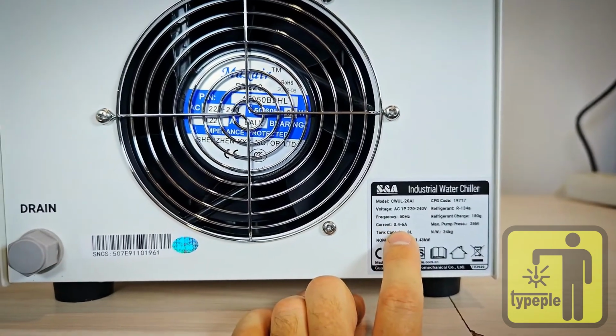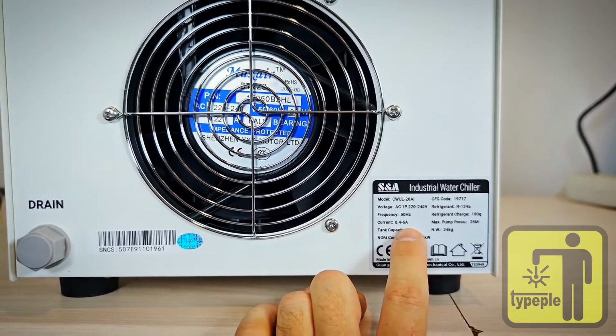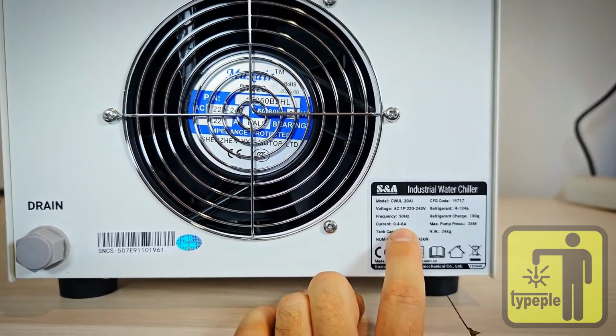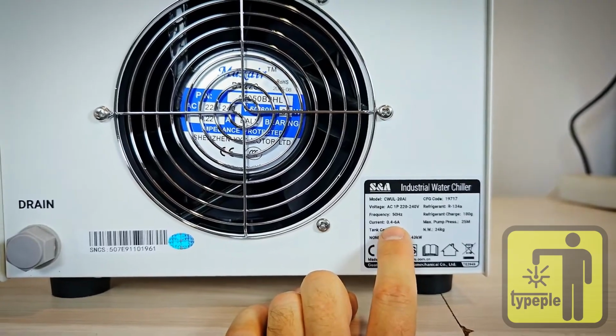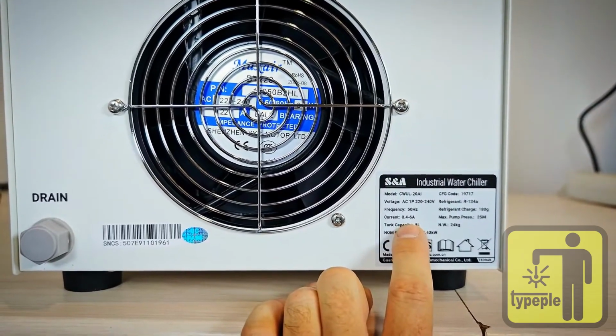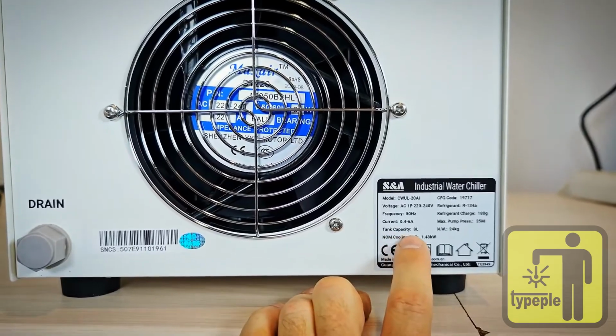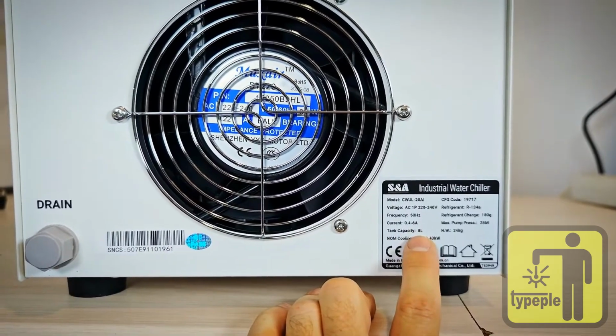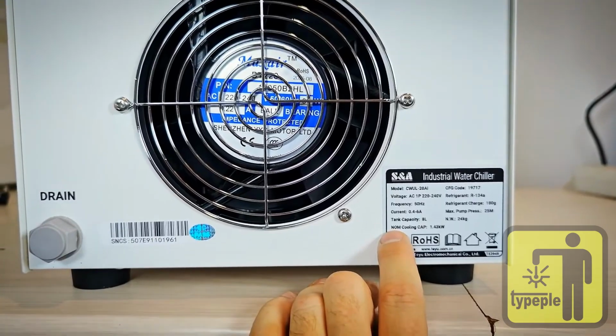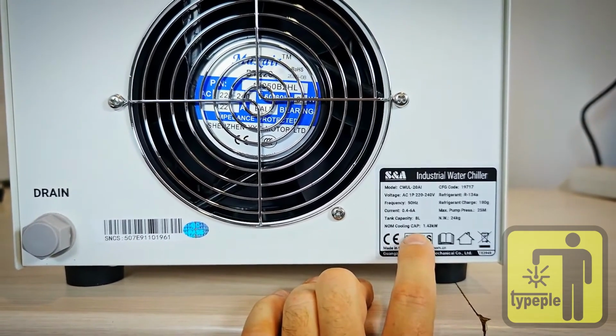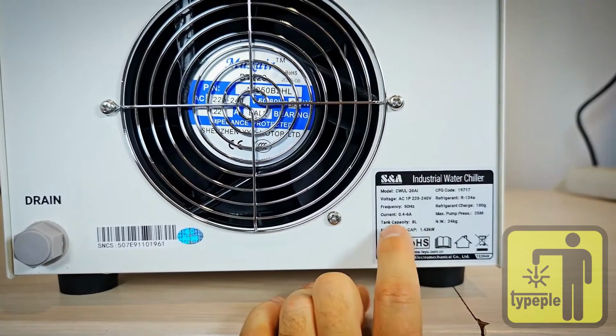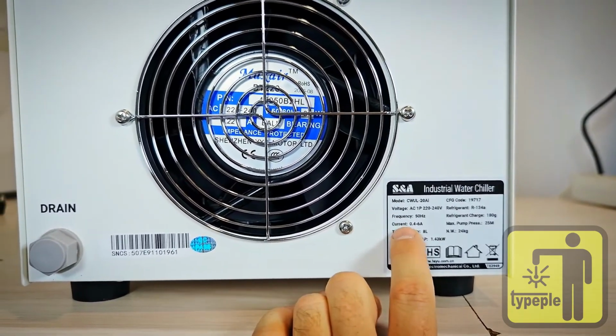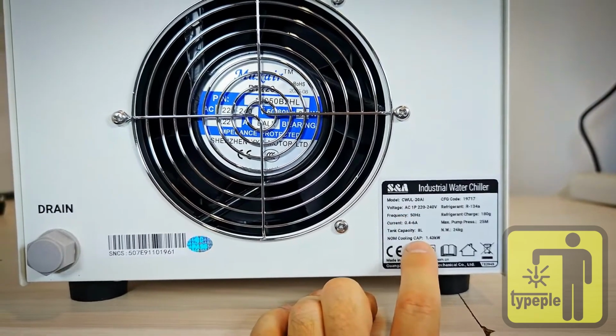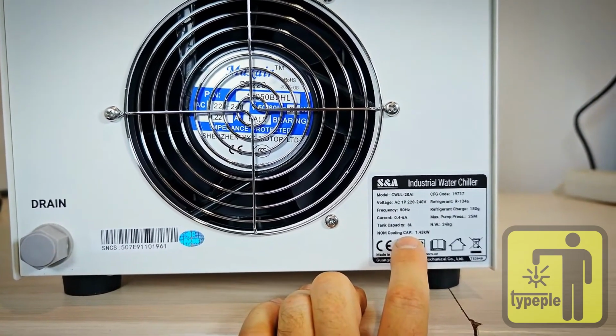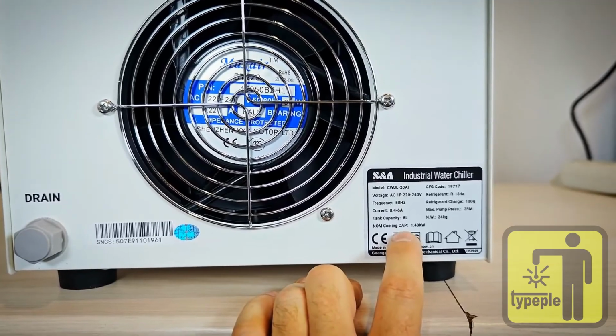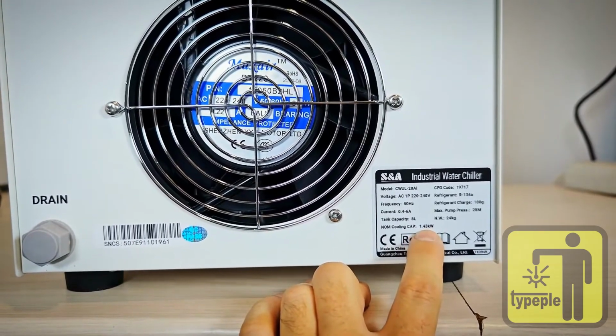Next, current consumption from 0.4 to 6 amps at 220 volts. We calculate that the average value comes out around 1.2 to 1.3 kilowatts. Tank capacity is 8 liters, so basically 2 5-liter jugs will be more than enough. Nominal cooling capacity is 1.43 kilowatts. Don't forget that here, regarding the current, it's a very interesting point, but here we have both a compressor and, accordingly, a heater. And if they work together, then it turns out we'll have 1.43 kilowatts.